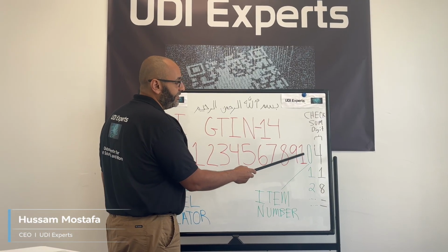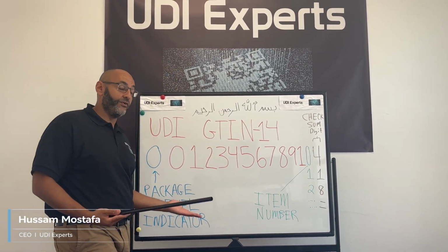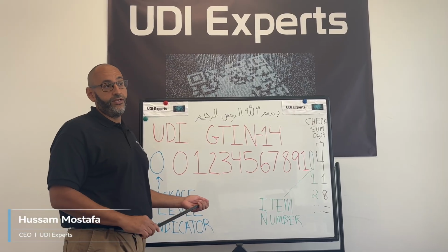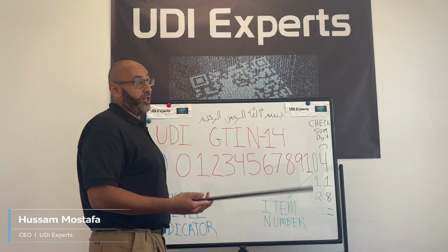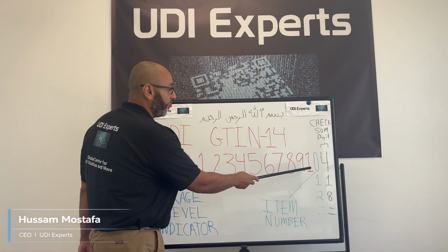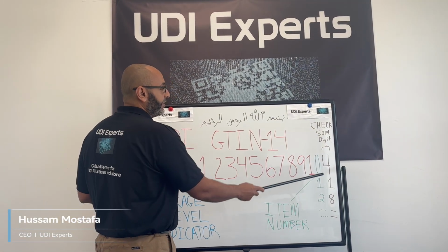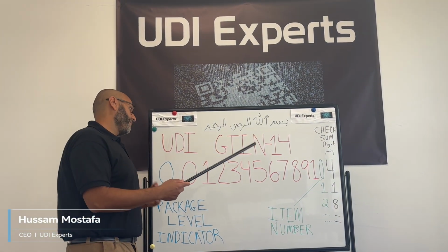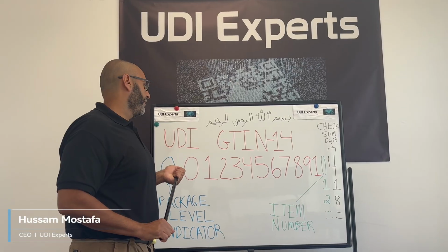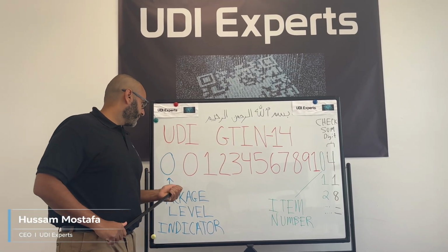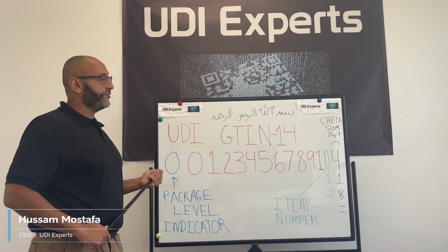But I had companies that, instead of keeping this reference item number for the box of gloves, they just change it, and in reality they're just wasting UDIs, because you could purchase 10 UDIs from GS1 and you could use them all maybe in 3 devices if you're always changing this number to identify the same device but in different packaging hierarchy levels. So that's a quick summary of UDI.